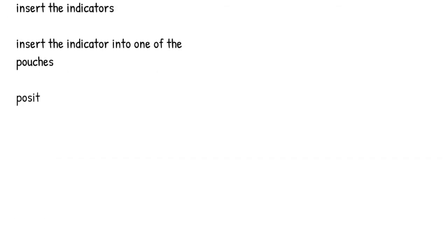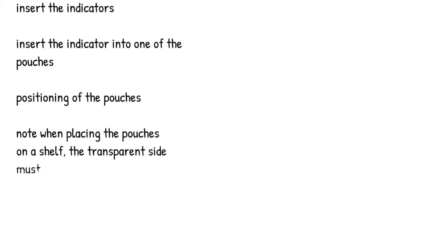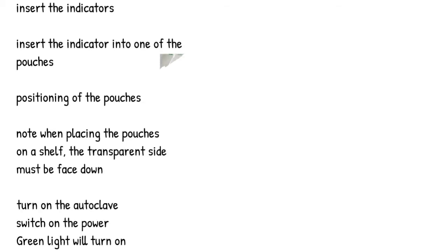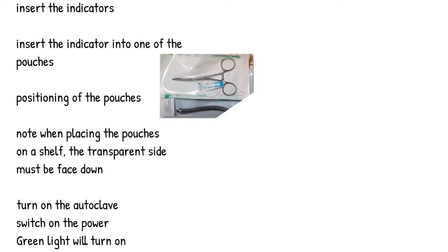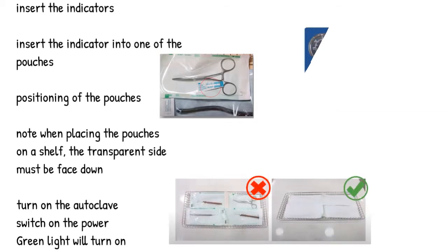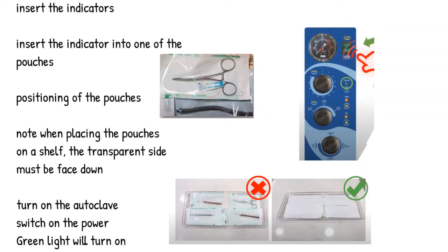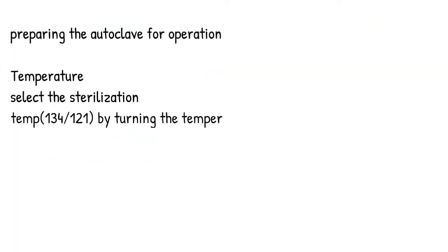Insert the indicators. Insert the indicator into one of the pouches. Positioning of the pouches: note that when placing the pouches on a shelf, the transparent side must be face down. Turn on the autoclave. Switch on the power, and a green light will turn on. Preparing the autoclave for operation.